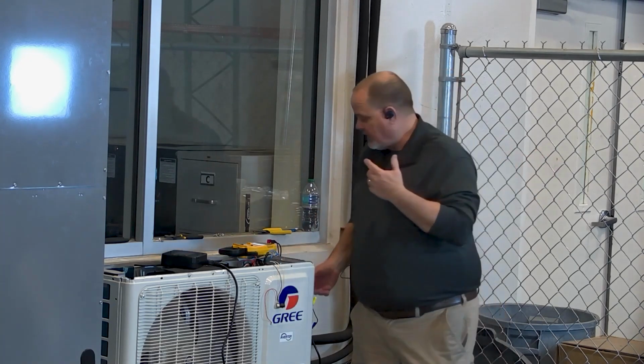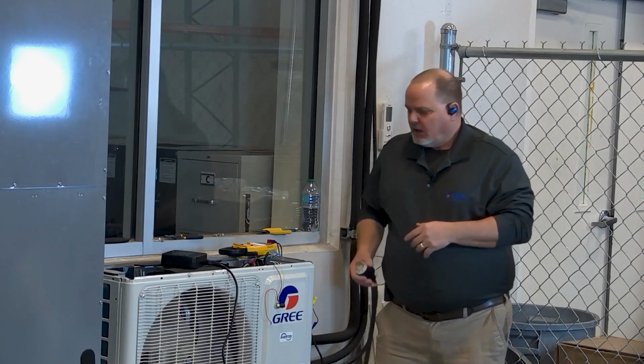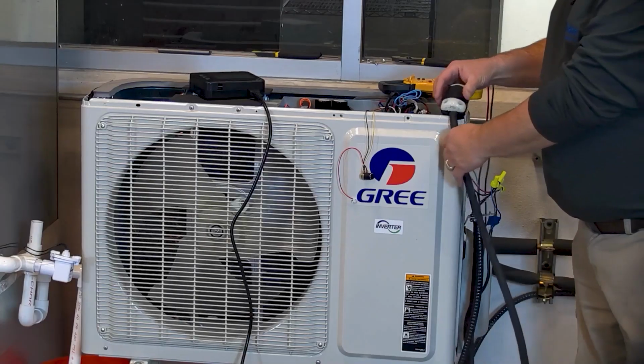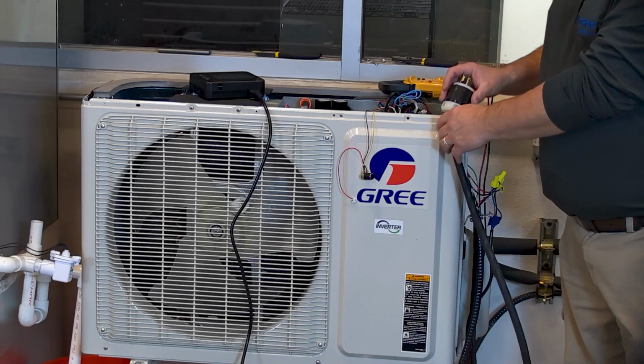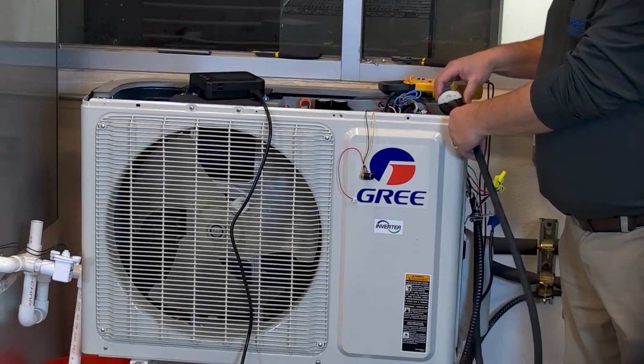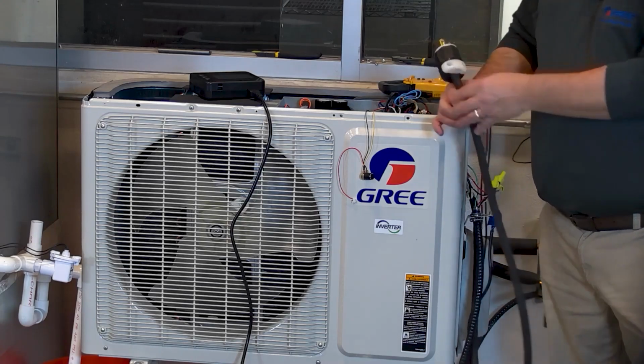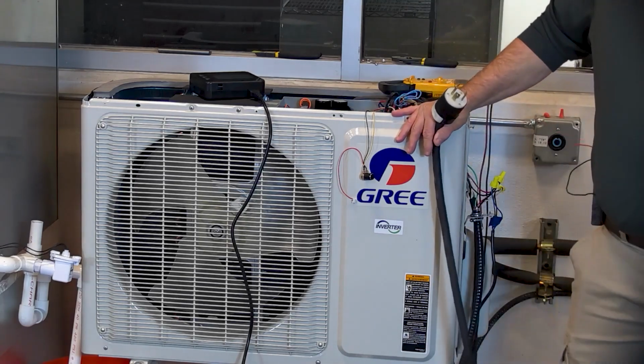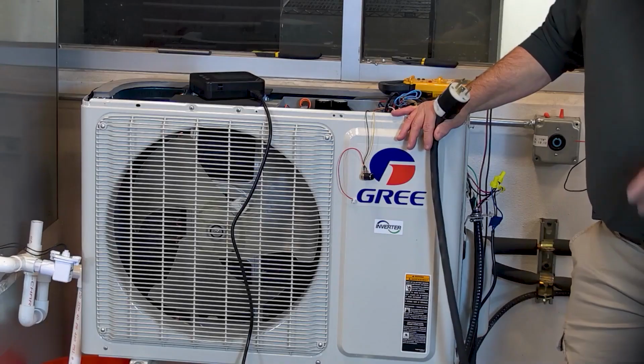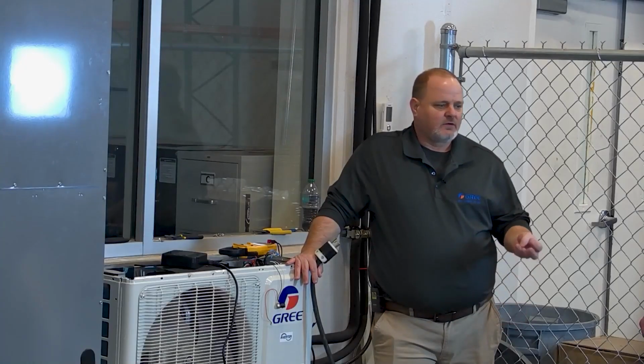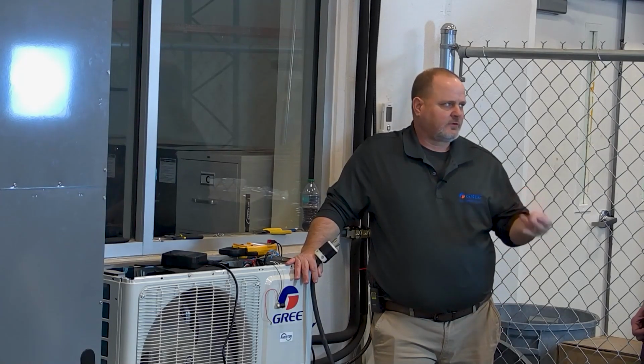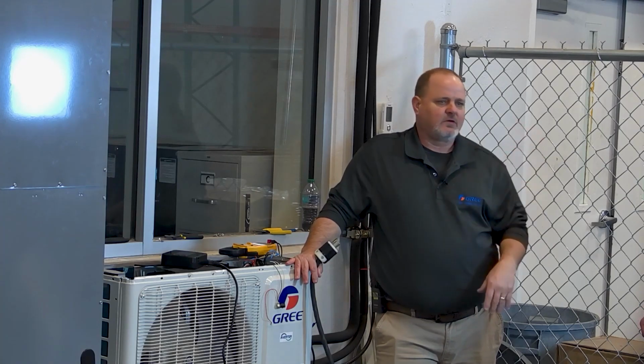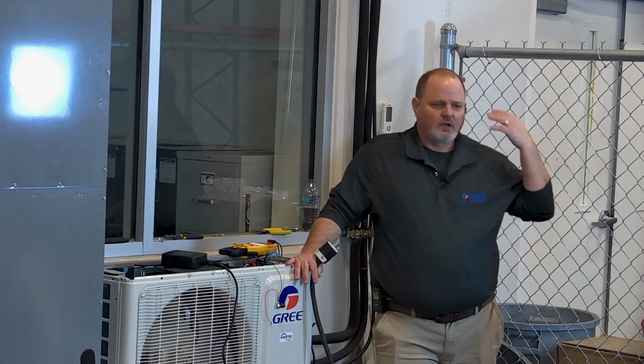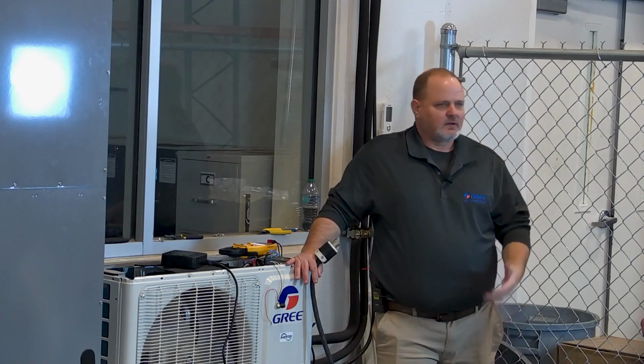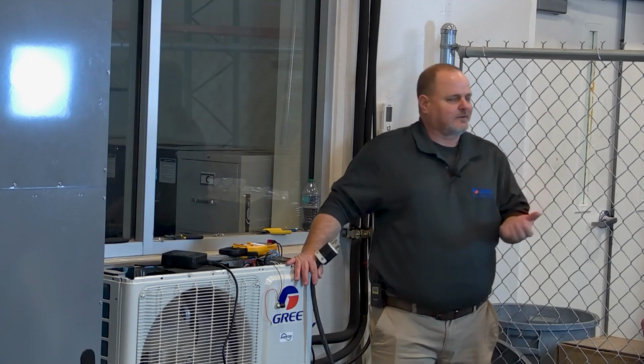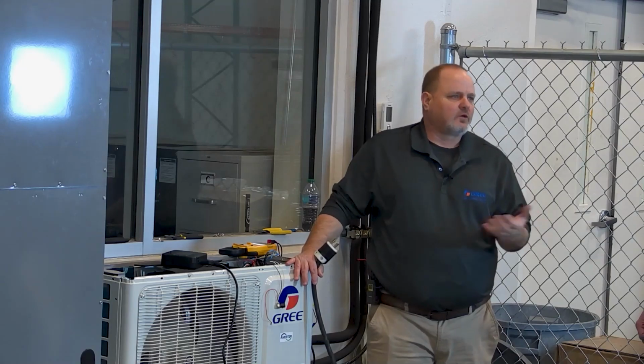So I'm going to go ahead and kill the power to it. But it probably has to have at least 2 or 3 high discharge temperatures before it's actually going to fault out and say, you know what, we tried to slow the thing down. The machine's thinking, we tried limiting the frequency of the compressor. We tried this, we tried that, and finally, we've done this 3 times. A service technician needs to look at it.